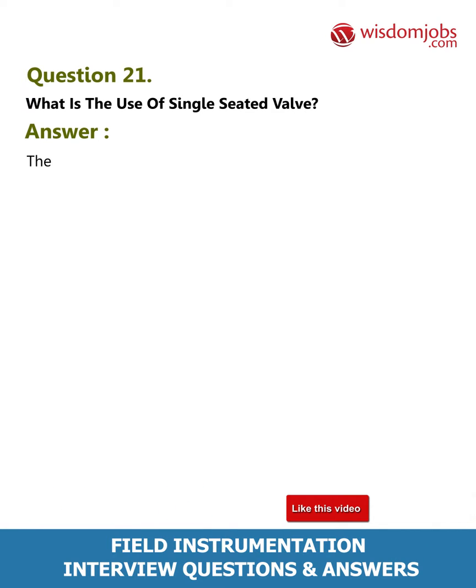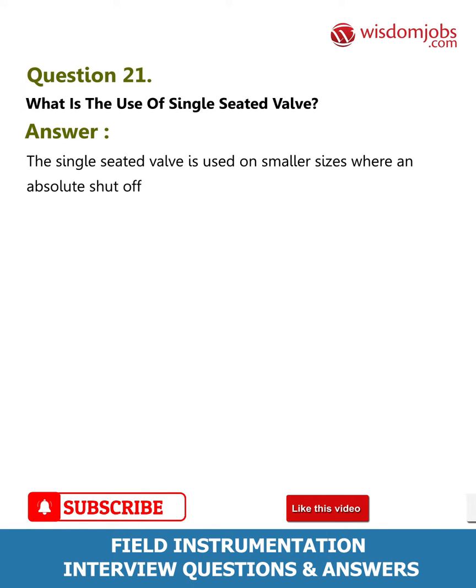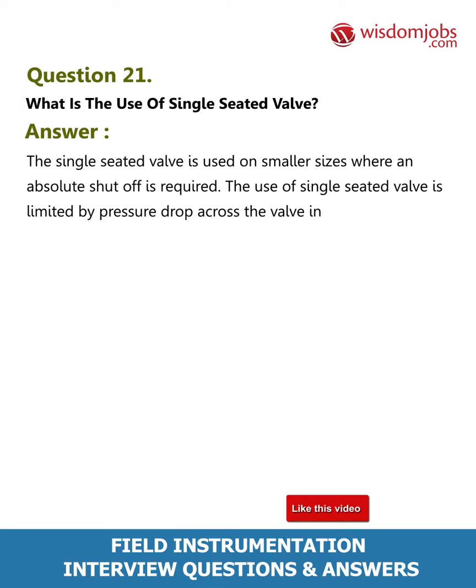Question 21: What is the use of a single seated valve? Answer: The single seated valve is used on smaller sizes where an absolute shutoff is required. The use of the single seated valve is limited by the pressure drop across the valve in the closed or almost closed position.